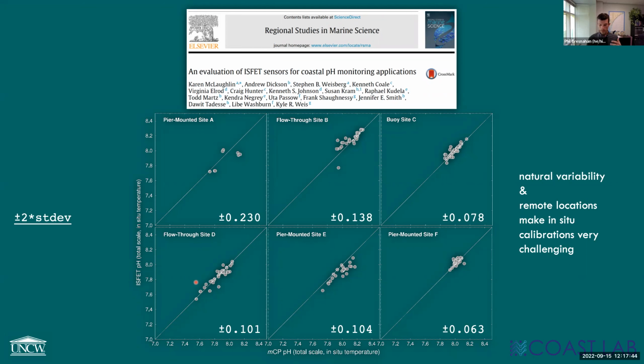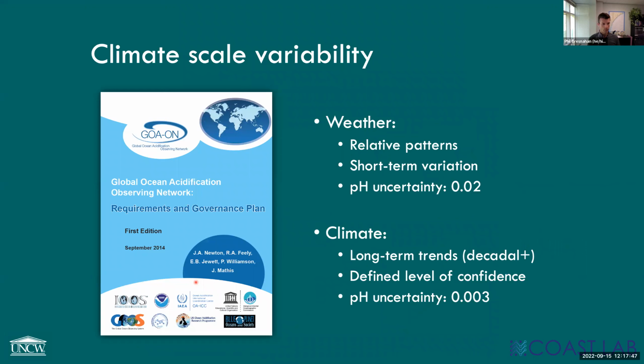A group of people put together this report, this governance plan, a few years ago, led by Jan Newton, Dick Feely, and others. And they wanted to say how we could define these different thresholds in pH, not thresholds in terms of when do ecosystems really start to feel the effects, but what can we call a pH uncertainty that's acceptable for understanding relative patterns and short-term variation versus climate scale changes, these 0.002 scale changes. And so they defined what they call a weather scale uncertainty, and they define what they call this climate scale uncertainty, so 0.02 and 0.003 here. And with these metrics in mind, we set forth to see what other ways we could come up with to really improve the accuracy of the DuraFet and this whole class of sensors.